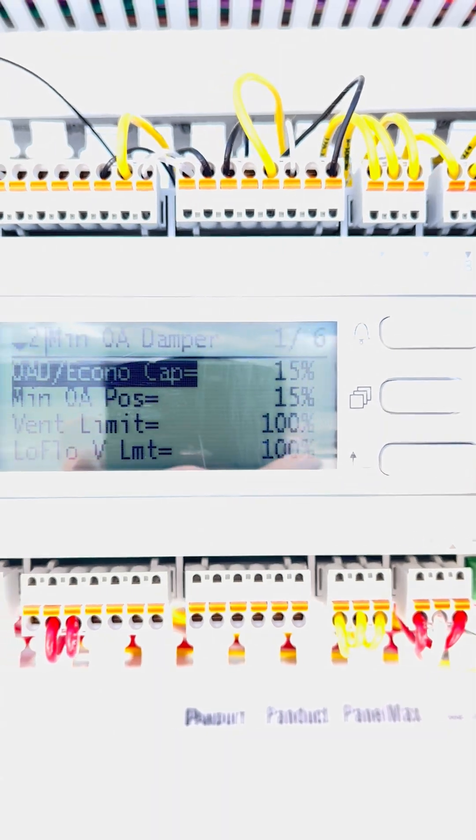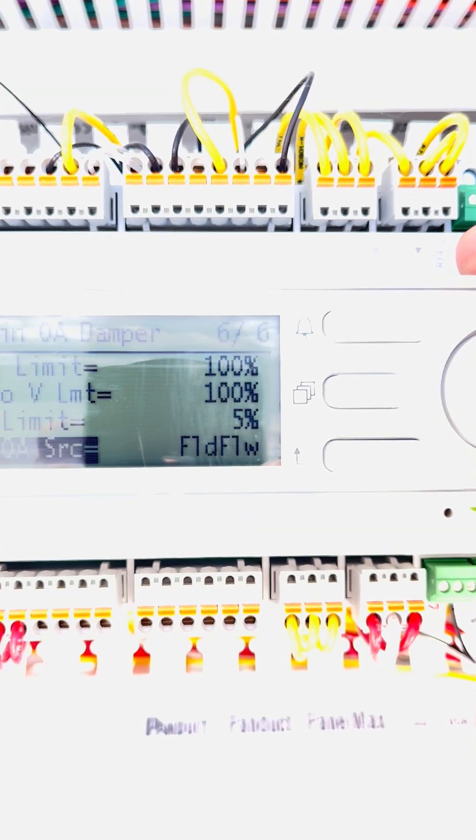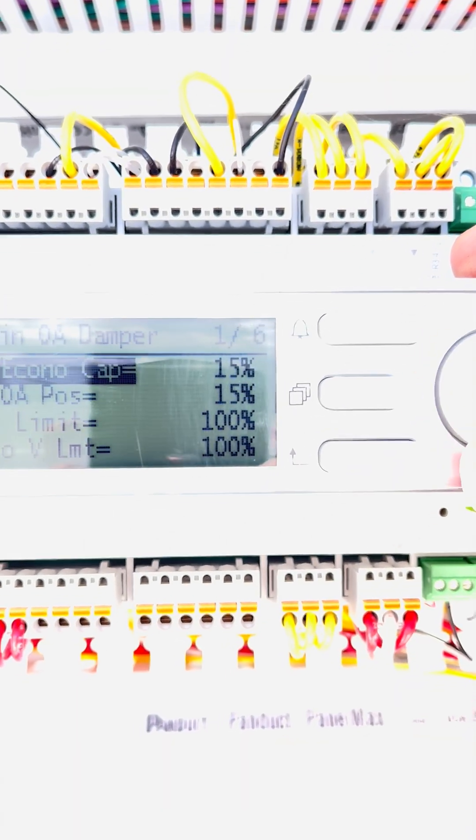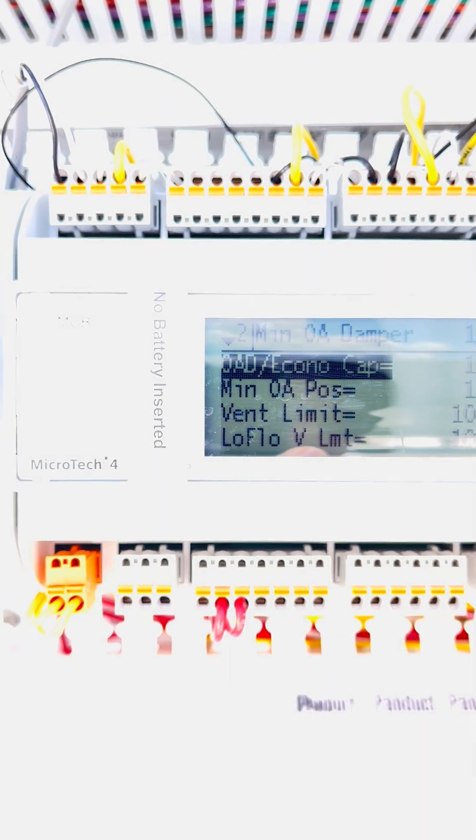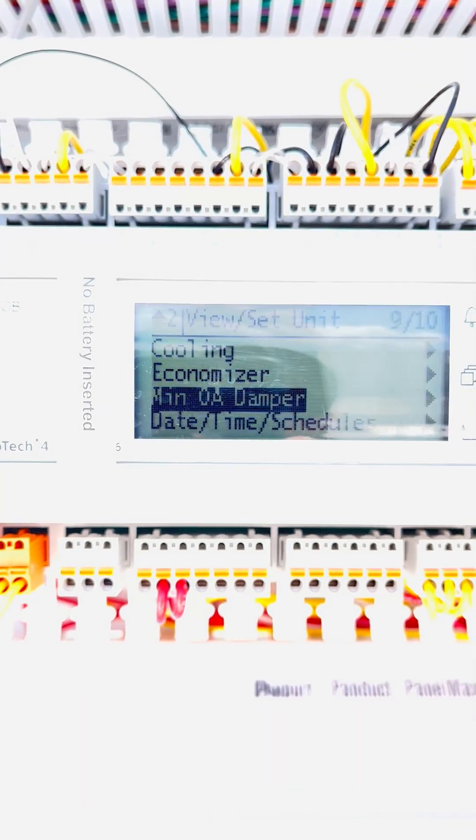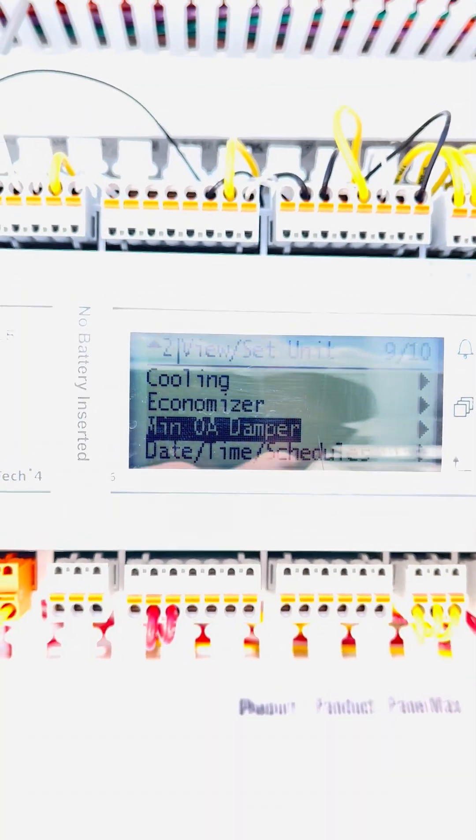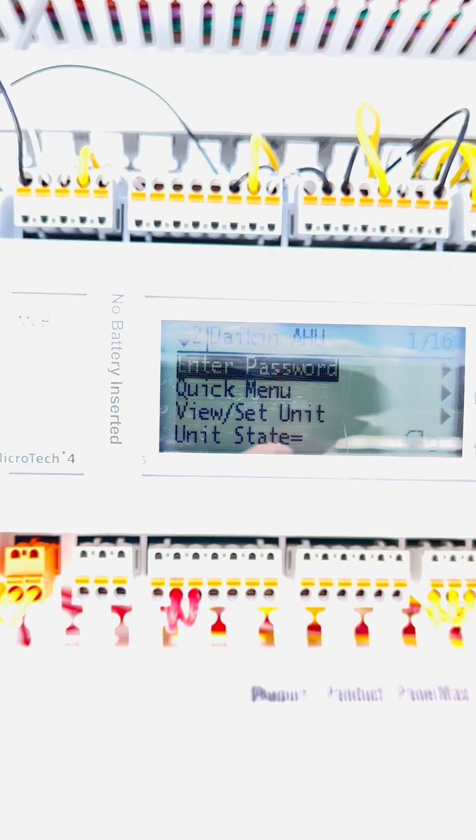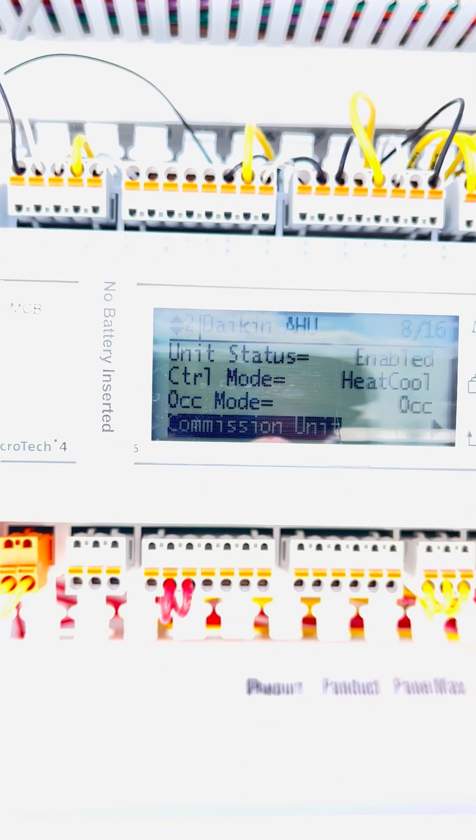So here, when we go back up, notice how it went to 15%. Well, that's because the field flow station is saying that it needs more airflow, so now it's modulating up. Now, again, this is in View/Set Unit in min outdoor air damper position.